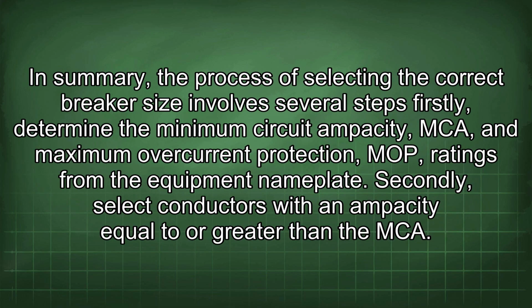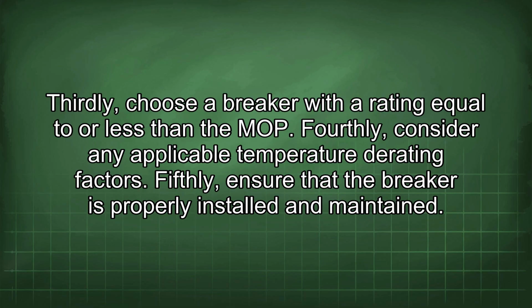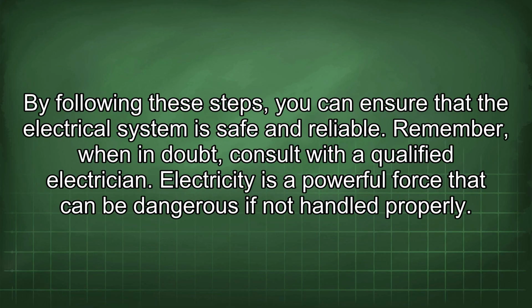In summary, the process of selecting the correct breaker size involves several steps. Firstly, determine the minimum circuit ampacity, MCA, and maximum overcurrent protection, MOP, ratings from the equipment nameplate. Secondly, select conductors with an ampacity equal to or greater than the MCA. Thirdly, choose a breaker with a rating equal to or less than the MOP. Fourthly, consider any applicable temperature derating factors. Fifthly, ensure that the breaker is properly installed and maintained. By following these steps, you can ensure that the electrical system is safe and reliable.